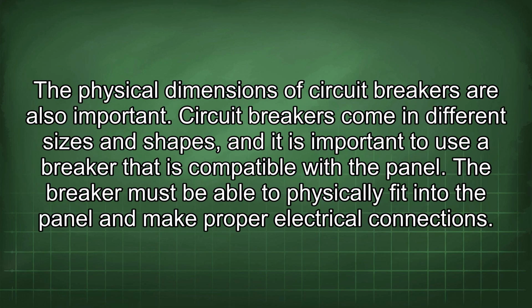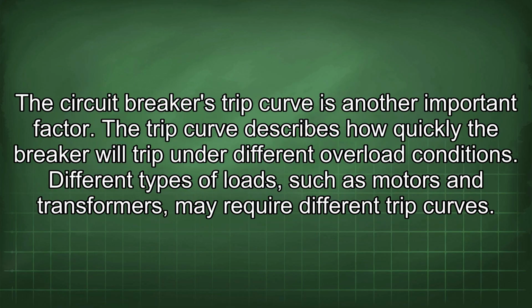The physical dimensions of circuit breakers are also important. Circuit breakers come in different sizes and shapes, and it is important to use a breaker that is compatible with the panel. The breaker must be able to physically fit into the panel and make proper electrical connections. The circuit breaker's trip curve is another important factor. The trip curve describes how quickly the breaker will trip under different overload conditions.